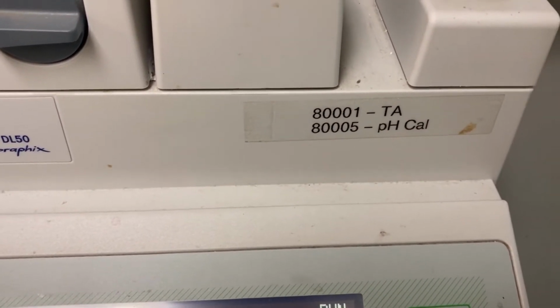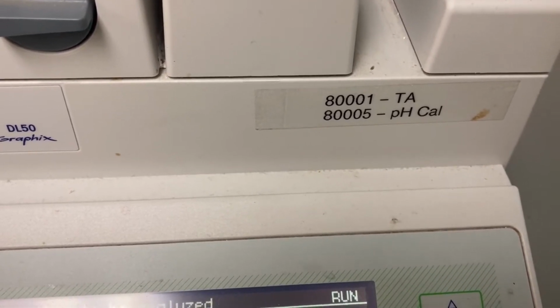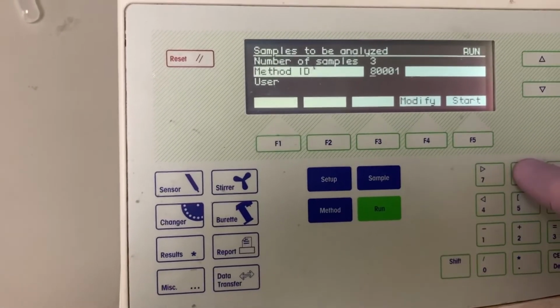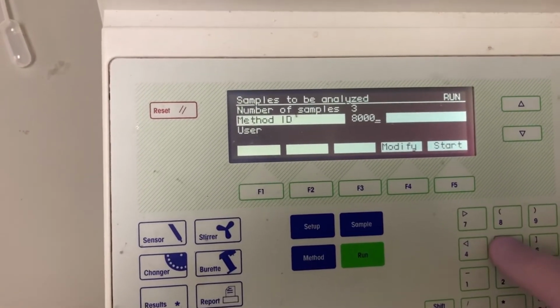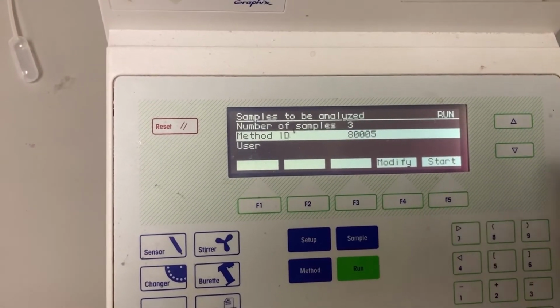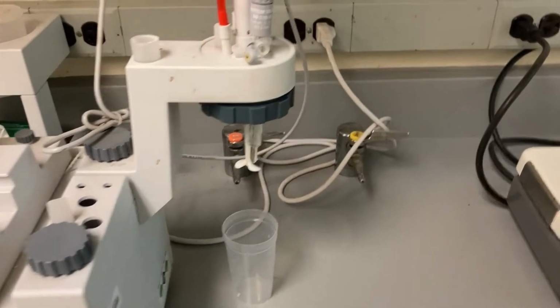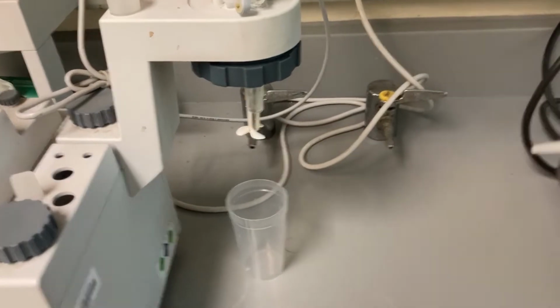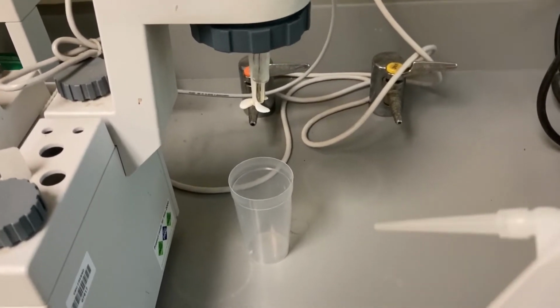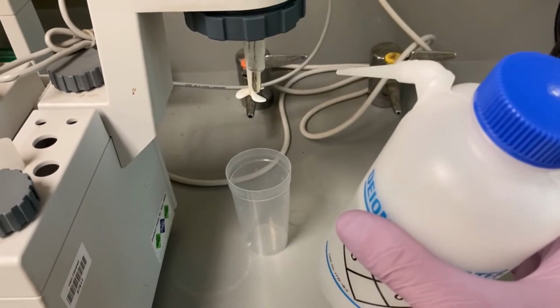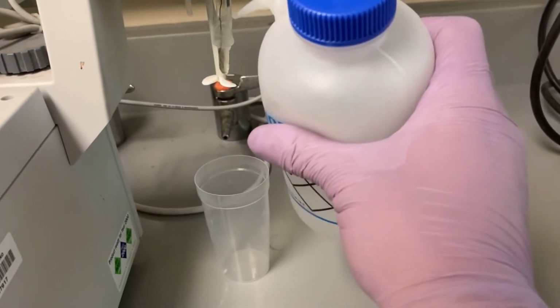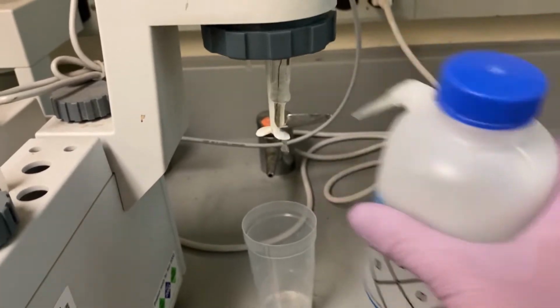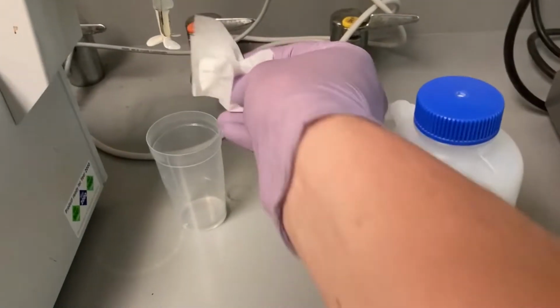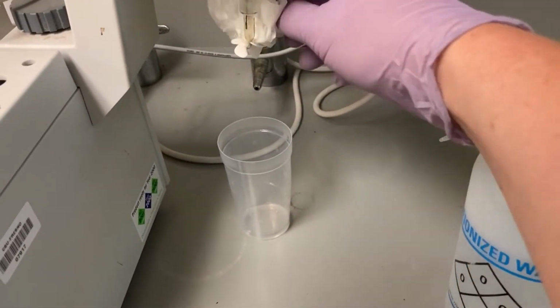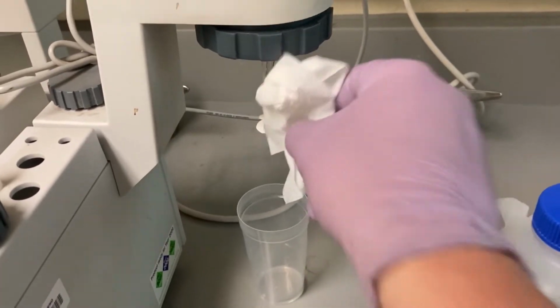So for calibrating, the method is 80005. So we can just enter that. And then hit start. Now keep in mind, before you do anything and in between every titration, you're going to want to wash the probe and pat it dry. I'm doing this with one hand, so it's a little awkward, but you can just take a chem wipe and then just gently dry it. You don't want to press it too hard.